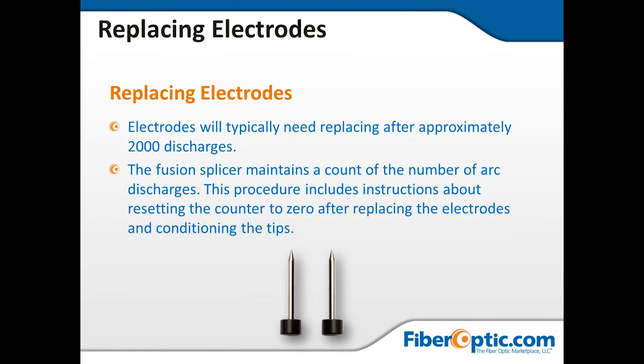And when it gets up there, the electrodes will have a certain color at the very tip that also is a sign to let you know, hey, these things may need to be replaced. And the Fusion Splicer maintains a count of the number of arc discharges. This procedure includes instructions about resetting the counter to 0 after replacing the electrodes and conditioning the tips.